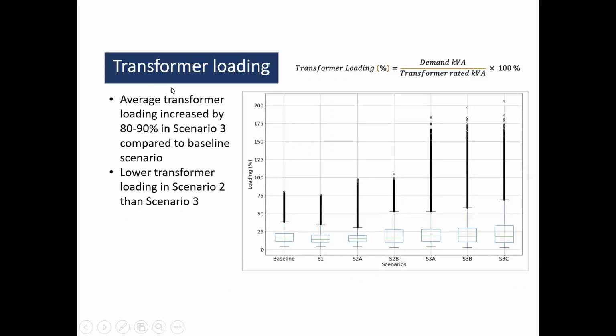And here's a slide on transformer loading. So the transformer loading is essentially a ratio of the demand kVA over the transformer capacity. In scenario 3, so this is all the scenarios plotted on one figure, in the scenario 3 cases, we see that the average transformer loading increased by 80 to 90% compared to the baseline. And there are numerous instances where the transformer is significantly overloaded in these scenarios.